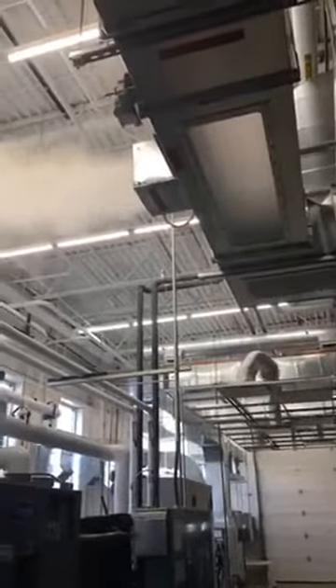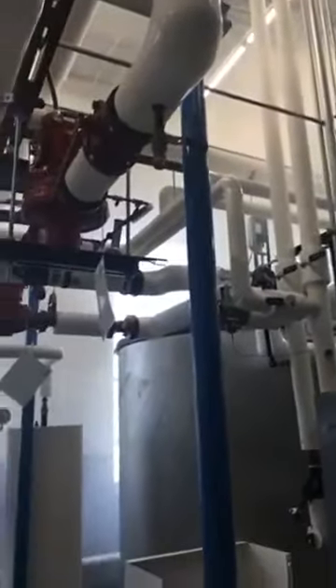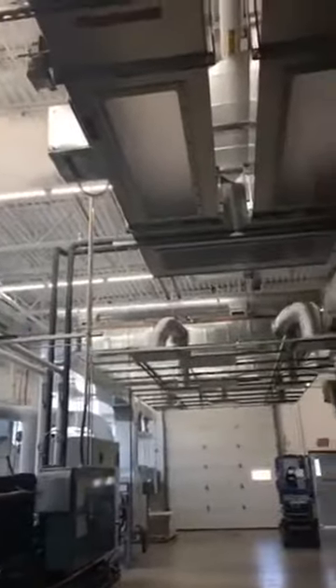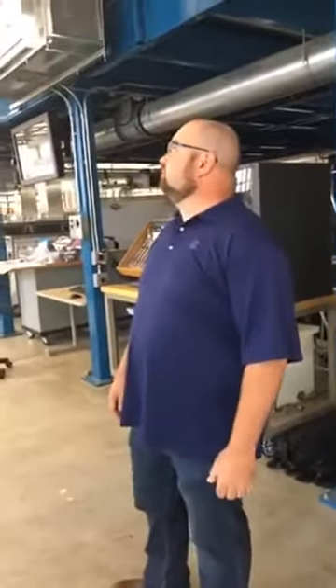This is what you'd be left with if you were in your room trying to leave without a working fire smoke system. Again, this is a non-toxic theatrical smoke we're using, but very quickly you can get the idea of what it would be like to be in a building that had a non-functioning fire smoke system. That would be a pretty typical duct size running to an office, a small apartment, even a hospital or a hotel room. It very quickly could be overcome with a non-functioning fire life safety system.